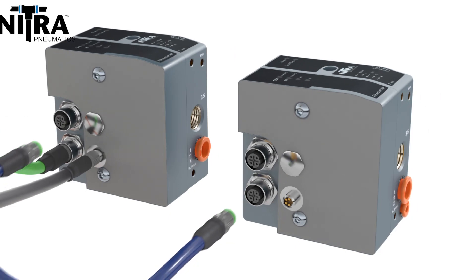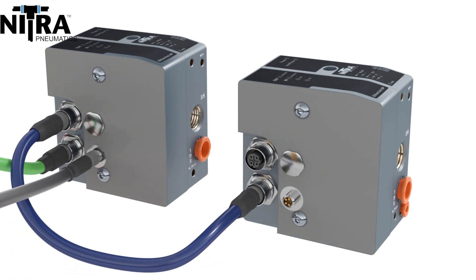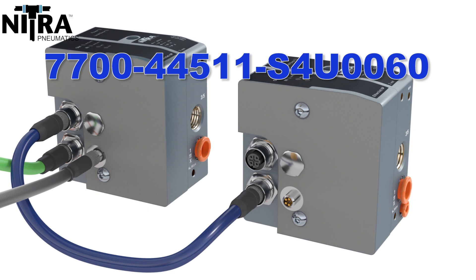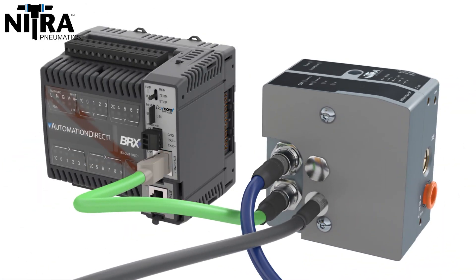The Ethernet IP modules can be daisy-chained by using one of our cables, like this model. AutomationDirect offers M12 Ethernet cables in several lengths with straight and 90-degree connectors. The number of Ethernet modules daisy-chained are limited by the number of IP addresses in a subnet. Don't forget to grab one of the communication Ethernet cables and power cables for the Ethernet modules. This cable connects from the control device to the first module on the communication drop.